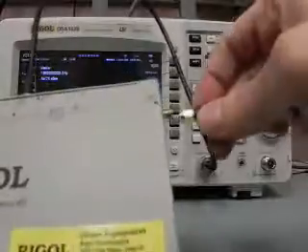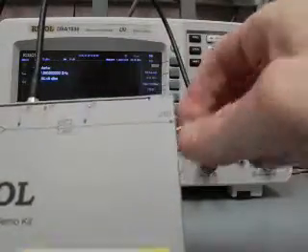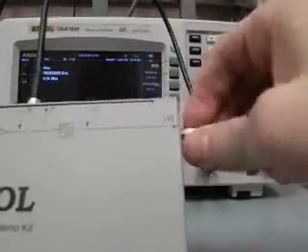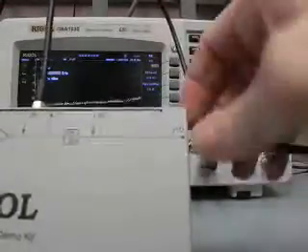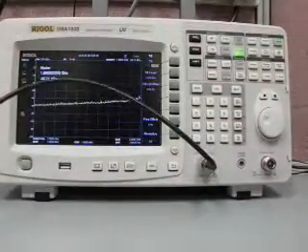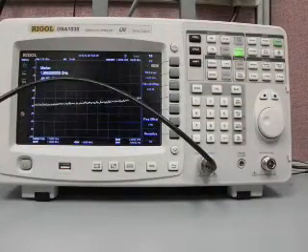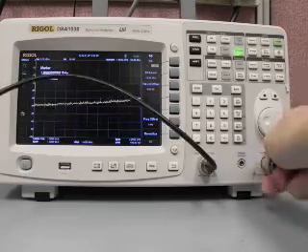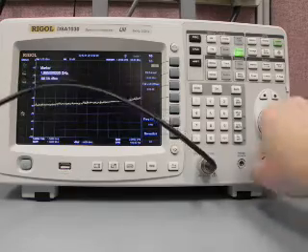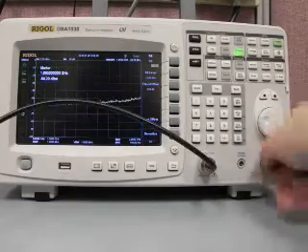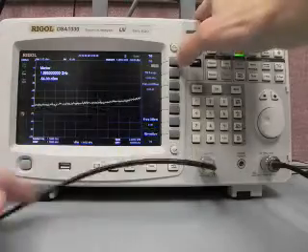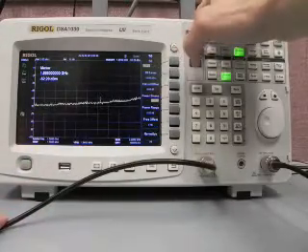So again, I don't have this connected to anything. It's not going to be actively creating any kind of signal. We're going to use the tracking generator through the filter to then characterize this filter. And so now we'll enable that tracking generator.